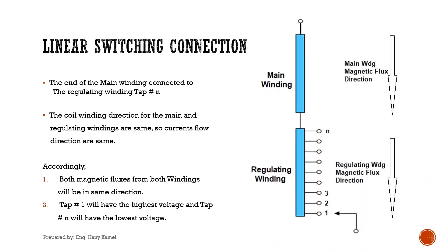We will start with linear switching connection. The end of the main winding is connected to the regulating winding at tap number N. The coil winding direction for the main and regulating windings are the same, so the current flow directions are the same. Accordingly, both magnetic fluxes from both windings will be in the same direction. Tap number 1 will have the highest voltage, and tap number N will have the lowest voltage.